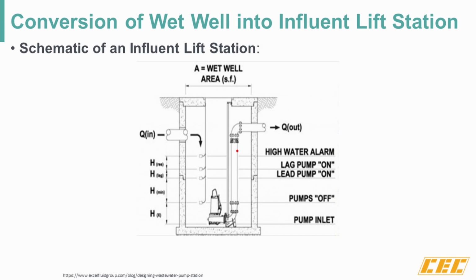Yes. So this slide just shows the schematic of the influent lift station. It essentially shows all the parameters that we considered in order to convert the wet well into an influent lift station. Eventually, the lift station will have 2 submersible pumps installed in it, and one pump will serve as a backup. And it will have control equipment, which essentially comprises alarm systems to warn us in case there is any very low or very high flow, just to ensure that the wet well is always at an optimum level for the water to be conveyed effectively.